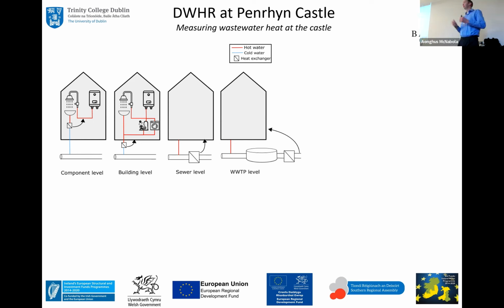I'll be further away from where that waste heat is generated, so it cools down by the time it goes from the shower to the collection point outside. But there'll be more waste heat density outside altogether, so there'll be a larger volume. The important thing in the energy available in wastewater is the volume of the water and the temperature. As you move away from the dishwasher, sink and so on, the temperature goes down but the volume goes up. Somewhere in the sewer system, there's a balance between where is the best place to capture all of that.